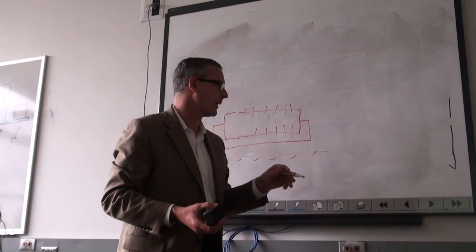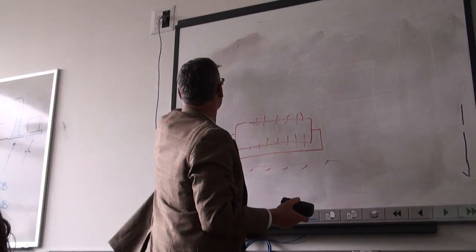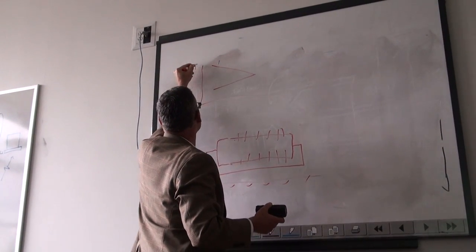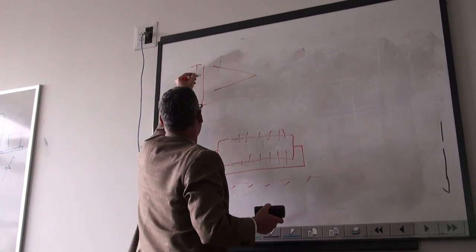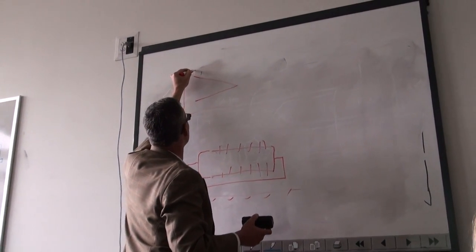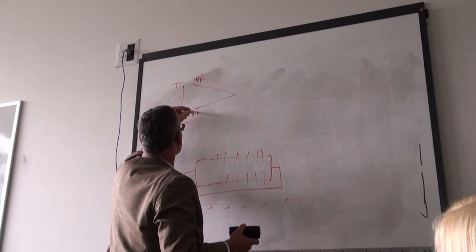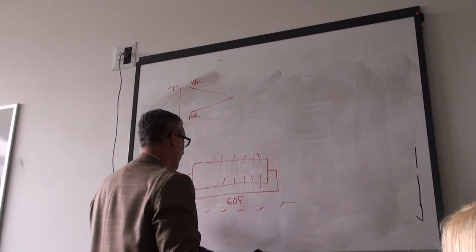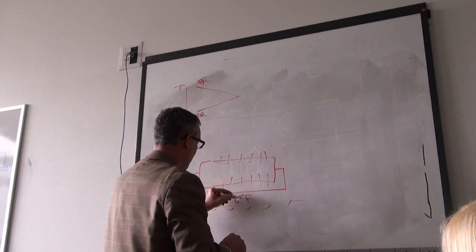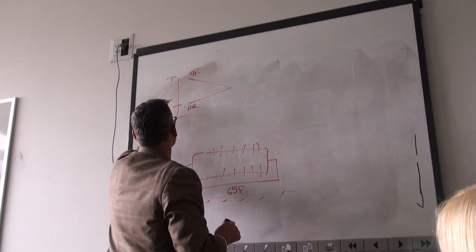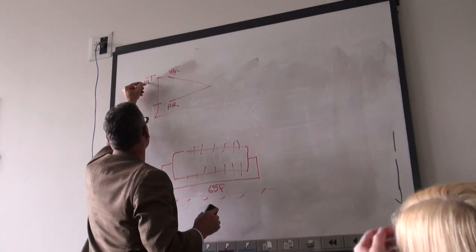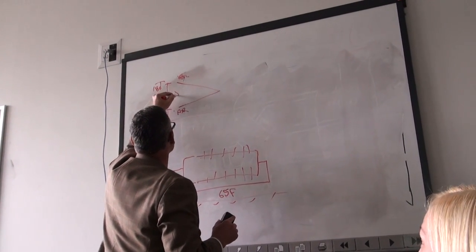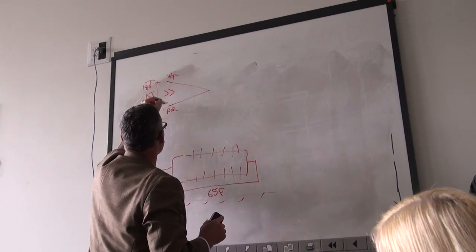You guys may have talked about log mean temperature difference. When a coil sees this, this is approach temperature. So this y-axis is temperature. This would be the water, and this would be the air. The air is typically about 60 degrees at the floor in a design for heating, maybe 65. In the old days, the water would be 180. This is a huge difference. You get a big delta T here, and lots of energy transmitted from the water to the air.